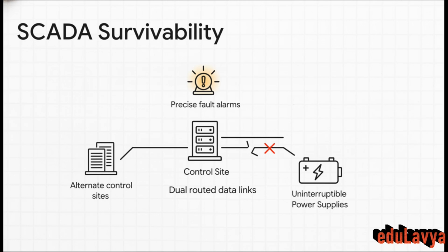It uses dual or multi-routed data links, meaning if one fiber optic cable gets severed in a crash, the data instantly takes a totally different physical route. There are alternate control sites ready to take over at a moment's notice, robust, precise alarms tell operators exactly where a break happened, and the whole system is backed up by uninterruptible power supplies, or UPS. So even if the entire grid fails, the control system stays fully alive.